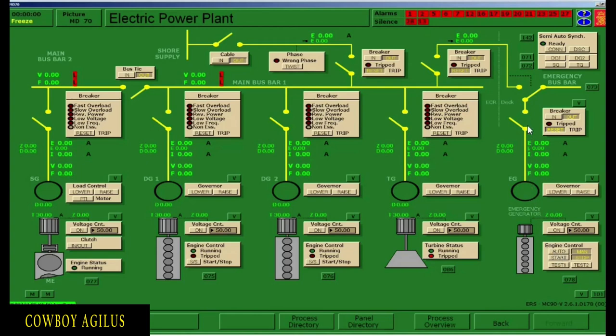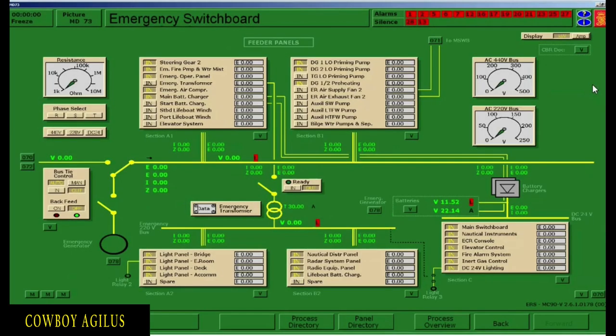Then proceed to number 73. This is the emergency switchboard — it is here where we will be supplying power to the consumers. Click number 73 and there is the emergency switchboard. In order to supply power to these consumers, click the button in. If the button is not pushed in, it will not be supplied with power. So go ahead and click all the buttons, since all of these are emergency equipment and they should always be supplied with power.